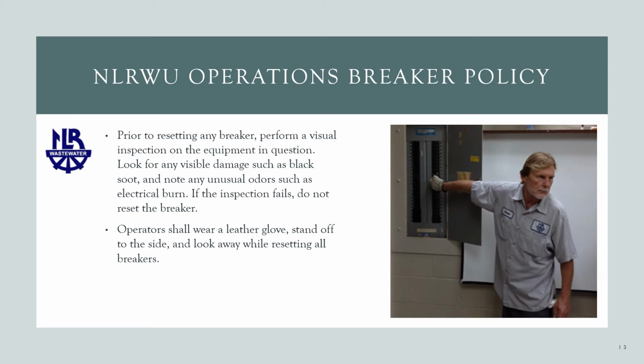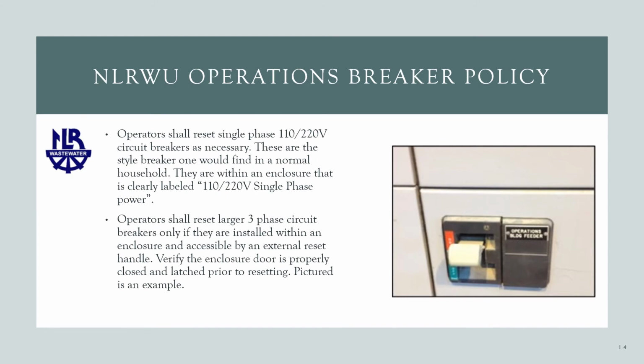Here's former operator David Johnson demonstrating proper technique. You should wear a leather glove, stand off to the side, and look away while resetting all breakers. Operators can reset single-phase 110 and 220 volt circuit breakers as necessary. These are your normal style breaker you'd find in a normal household. They should be within an enclosure that's clearly labeled 110, 220 volt single-phase power.